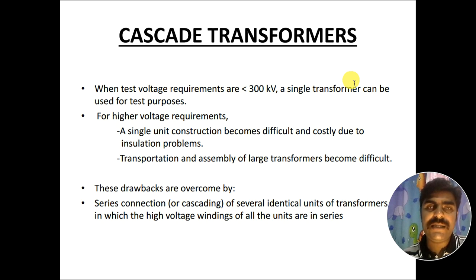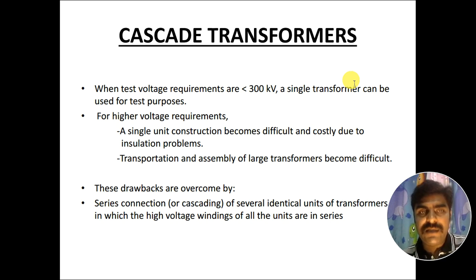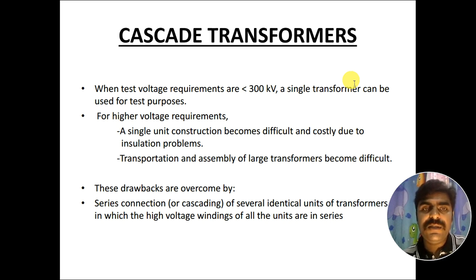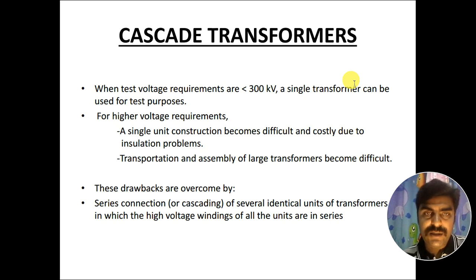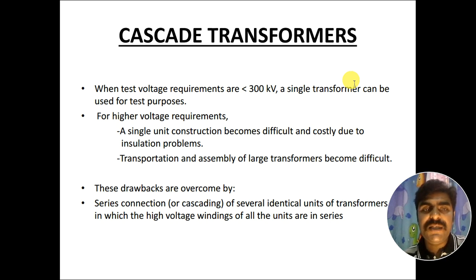But if the testing requirement is more than 300 kV, as we have in EHV or UHV lines, a single transformer will not be sufficient. The reason is that single unit construction becomes difficult and its cost is also high. Another issue is the insulation problem — designing a transformer for more than 300 kV creates serious insulation challenges. Additionally, transportation and assembly of such large transformers is also difficult.